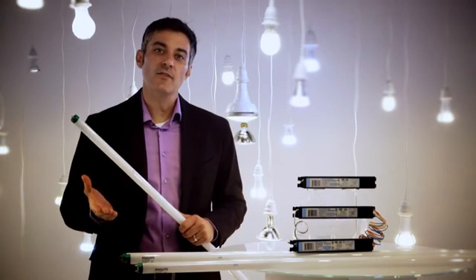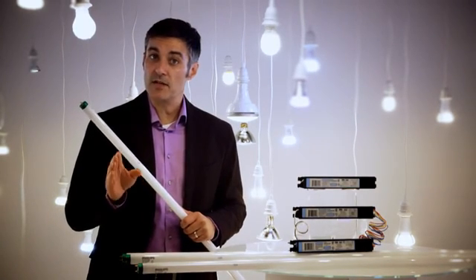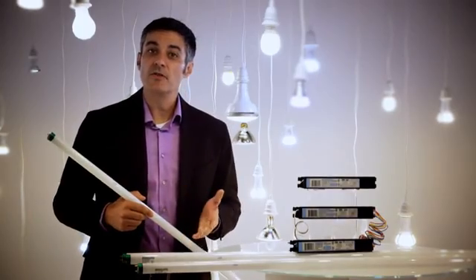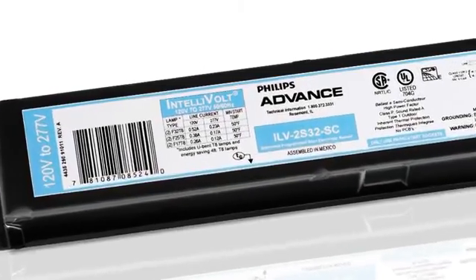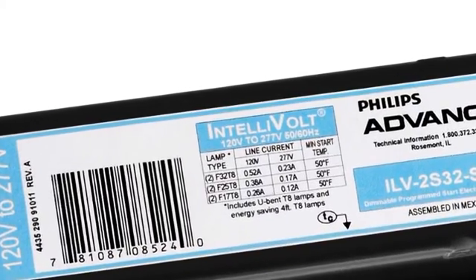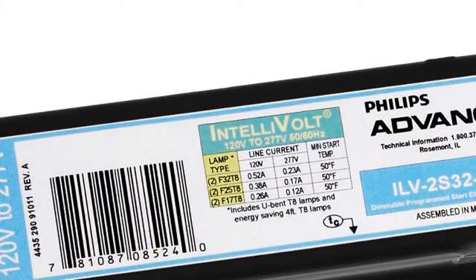To determine which kind of ballast you need to purchase to replace a current installation, first check out the label. Any existing ballast should have all of the information you need. The input voltage, lamp type, and the number of lamps it operates.